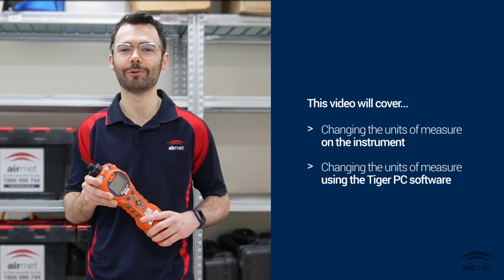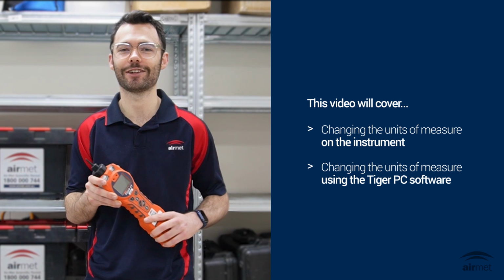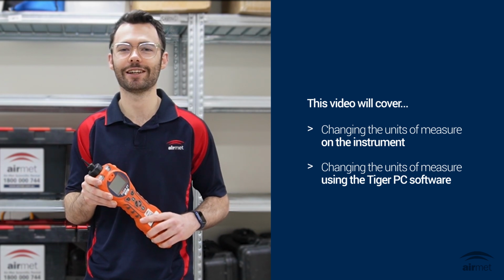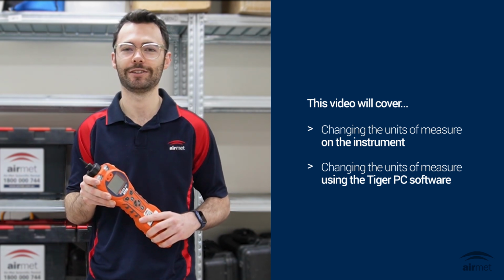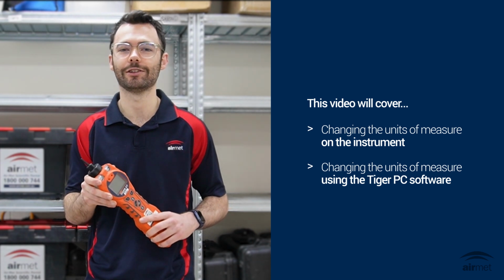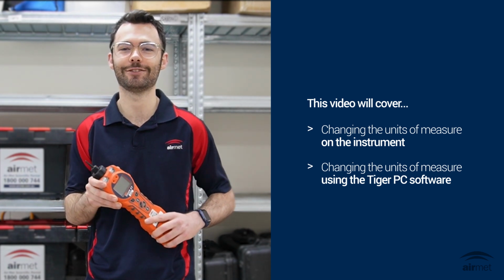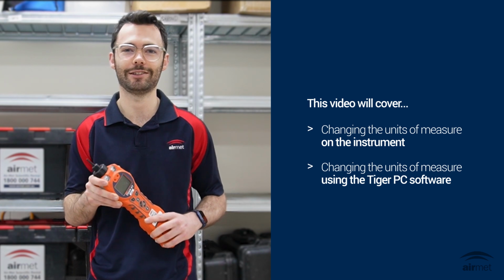For example, if you are working in an environment where VOC concentration is very low, you may need to change the unit of measure to ppb. In this video, I will demonstrate how you can change the unit of measure on your Tiger XT device itself and using the Tiger PC software.